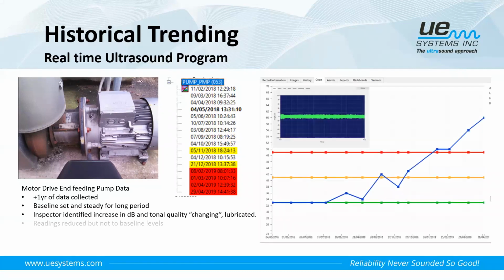So the baseline was set and was steady for a period of time, and we can start to see the decibel level increasing over time. We can see from the baseline and from the time waveform we see on the screen there, smooth and uniform to begin with, and then it started to increase.